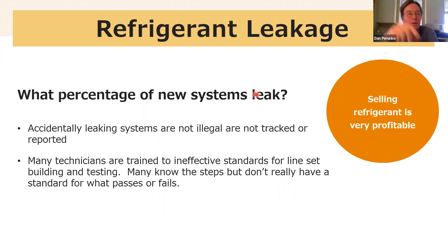So I said this earlier, I got a little ahead of myself. There's no tracking of accidentally leaking systems. And when I go out and talk to technicians, they know that what they're doing is important, and they'll be doing a test to make sure that the line set's going to be tight, and they really aren't sure whether their system is passing the test or not. And so they'll do whatever it is for a while, and then they'll just go, okay, well, that's good. They don't have a clear pass-fail. They don't have a clear metric for did this system pass and is safe to use, or is this system going to be an issue? And I'm not trying to say these people are jerks. These are nice people that I have worked with and that I'm fond of, that at their level of training and understanding had no idea if they were succeeding. And their job was to build these things every day.